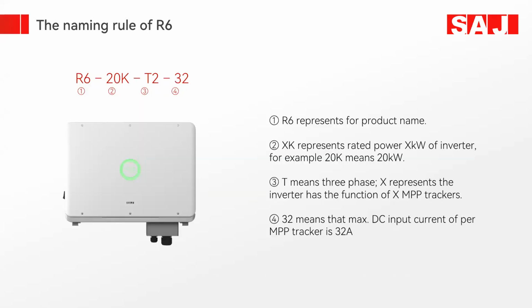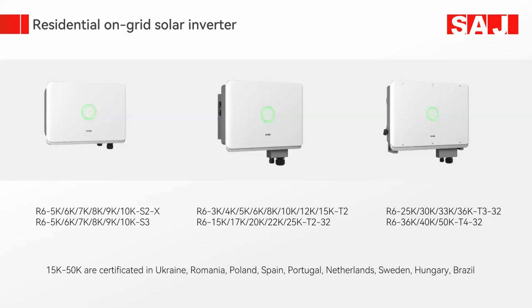According to the Pakistan market, we have a 32 ampere MPPT tracker, and the panels coming in the Pakistan market have a higher ampere rating. So customers can connect those panels with our R6 series inverters. For residential on-grid solar inverters, if we talk about single phase, R6 5 kilowatt, 6 kilowatt, 7, 8, 9, 10, and S2. S2 means single phase and 2 MPPT.